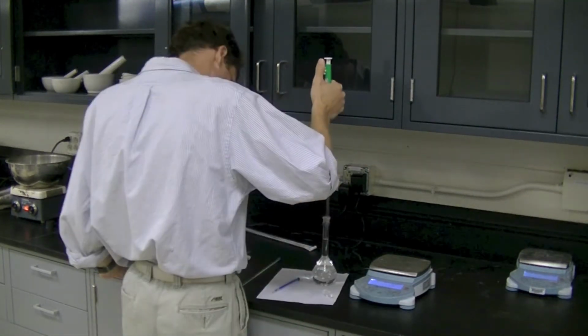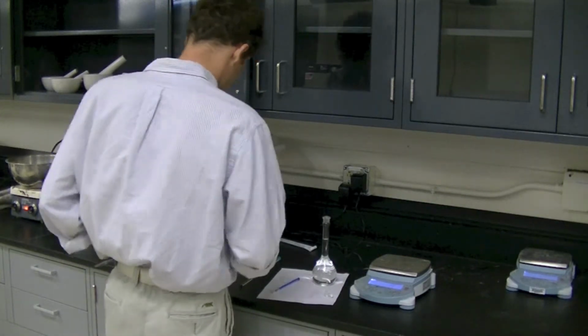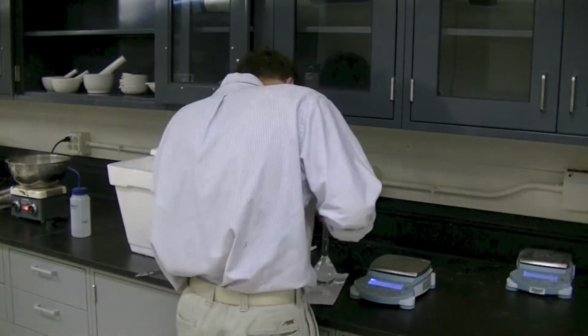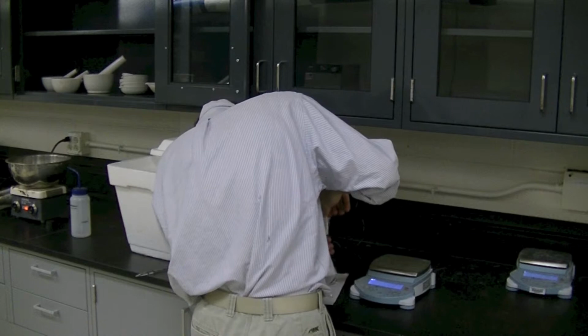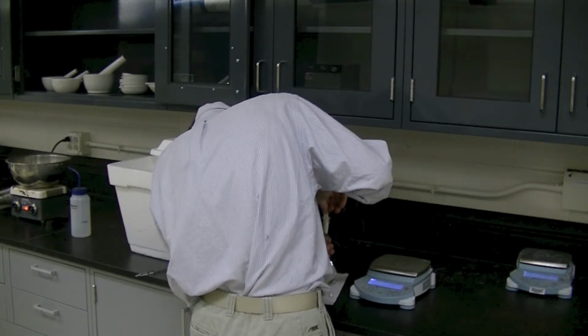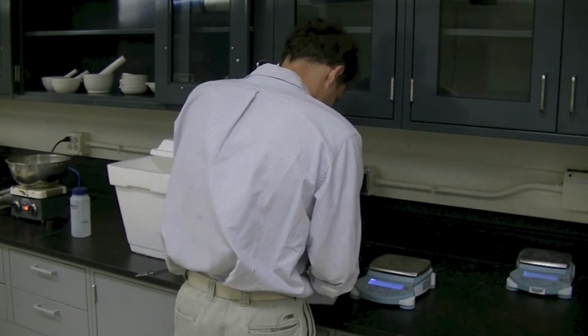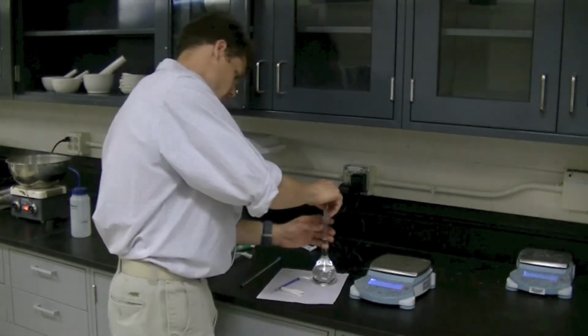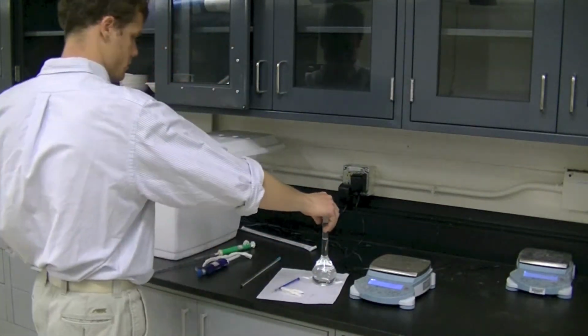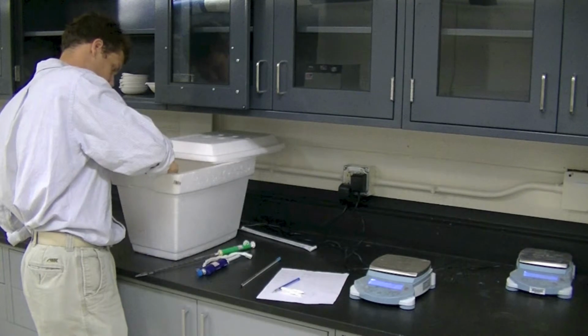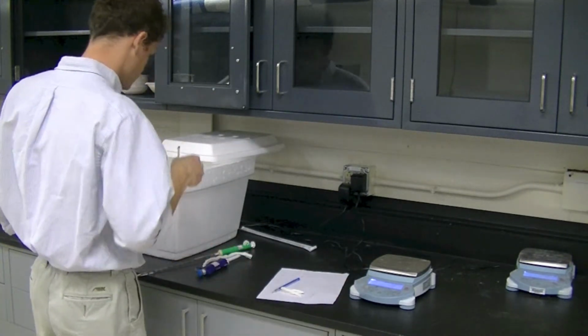Readjust the water level up or down for the next calibration. Place the full pycnometer, thermometer, and extra water inside the insulated container and allow for another 3 hours to pass. Thermal equilibrium will again be met. Repeat the process 4 more times for a total of 5 volume measurements.